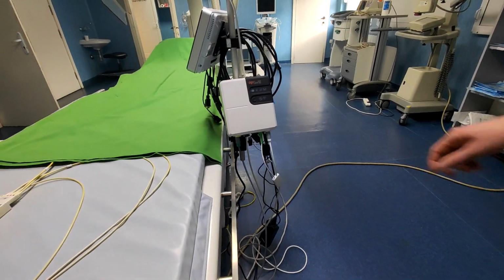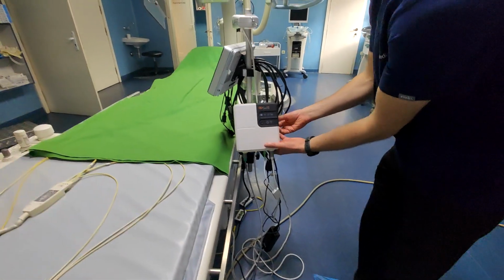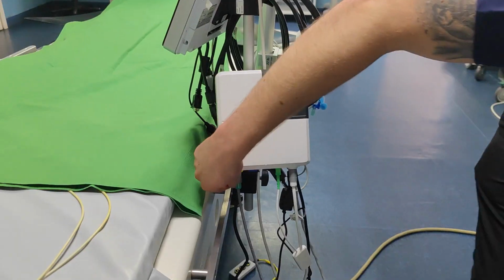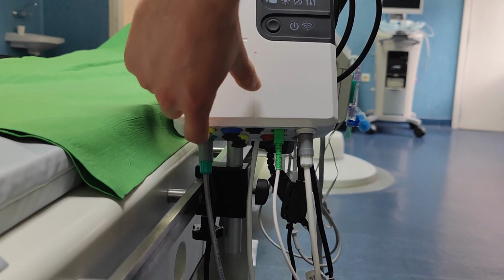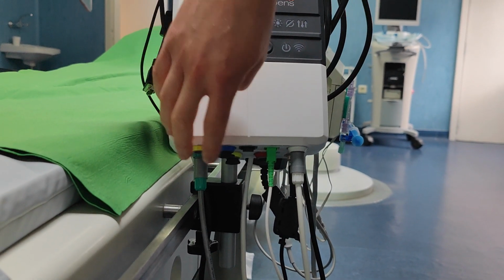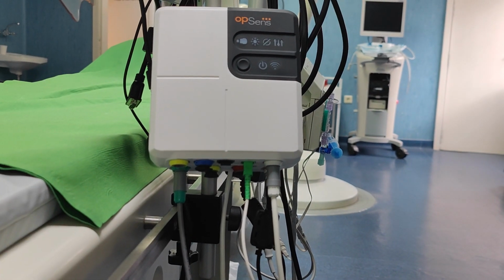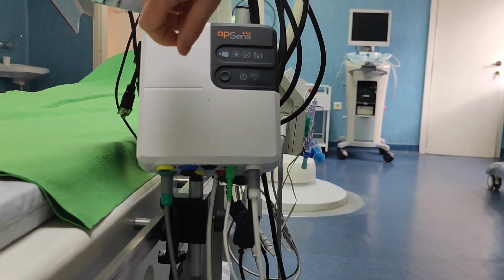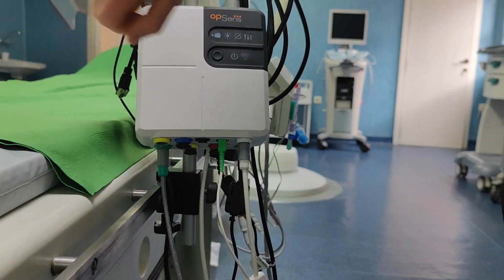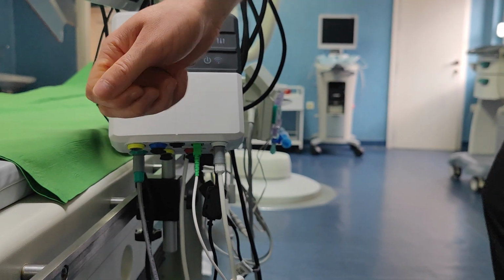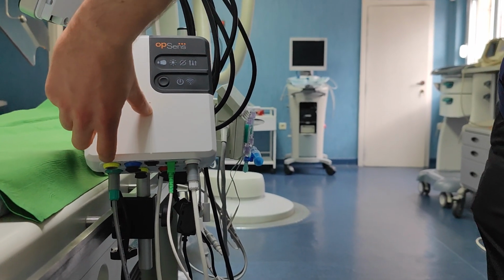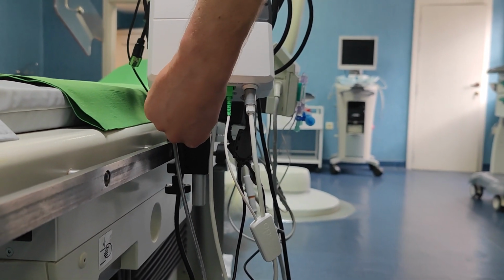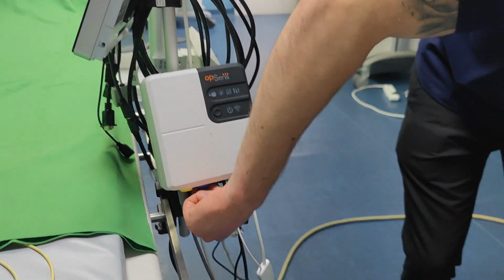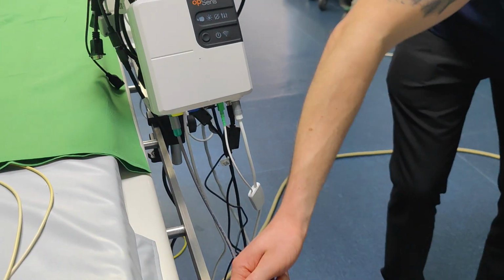setups simultaneously. So all the ports on the optical unit are color coded. The color of the cable lines up with the color of the port. Now, one to be wary of is the two yellow ports. If you're doing a transducer setup, direct from the transducer, which takes the aortic signal into this, then we have to output that aortic signal from the transducer into their HEMO system. So there's two ports. There's a yellow port, which is the distal out, and there's one that's the aortic out. In that setup, you want the aortic output, and the yellow cable plugs the aortic output into their HEMO system.